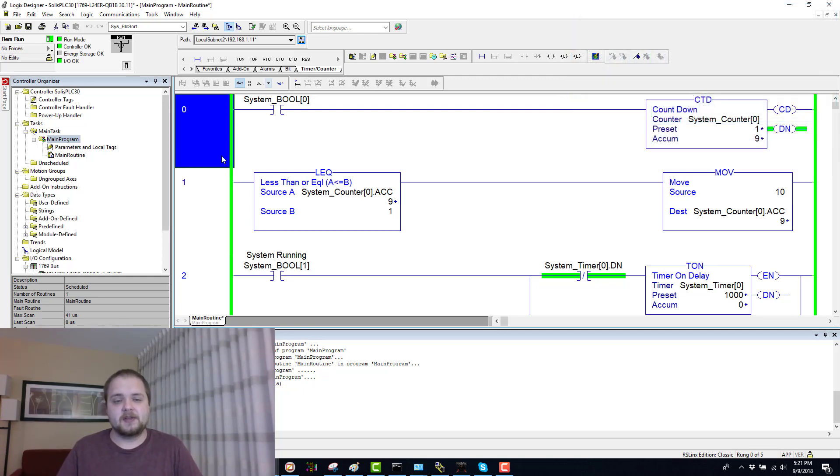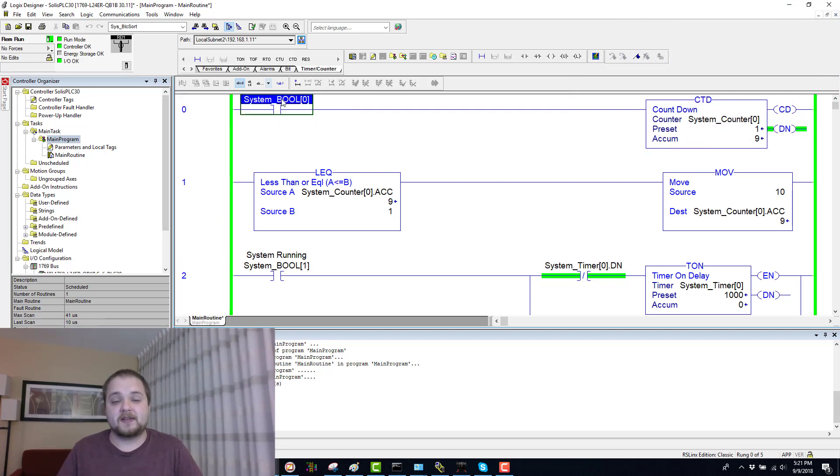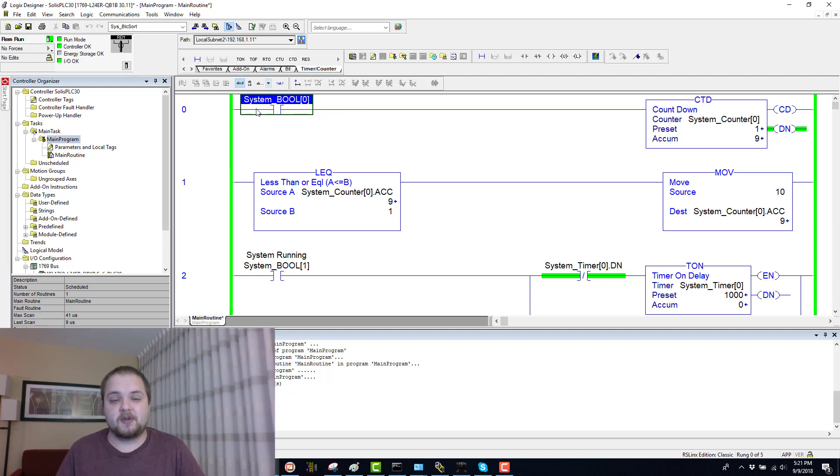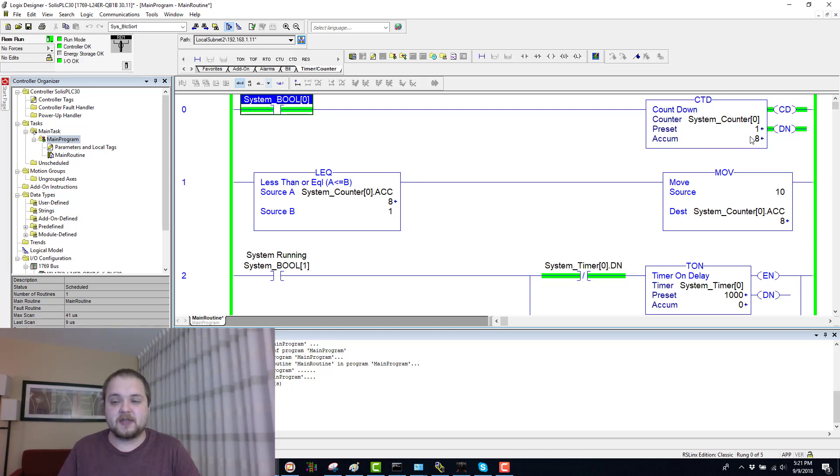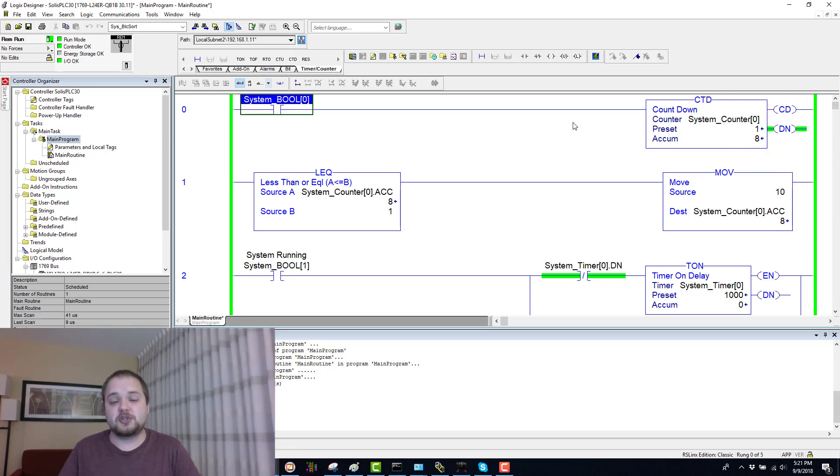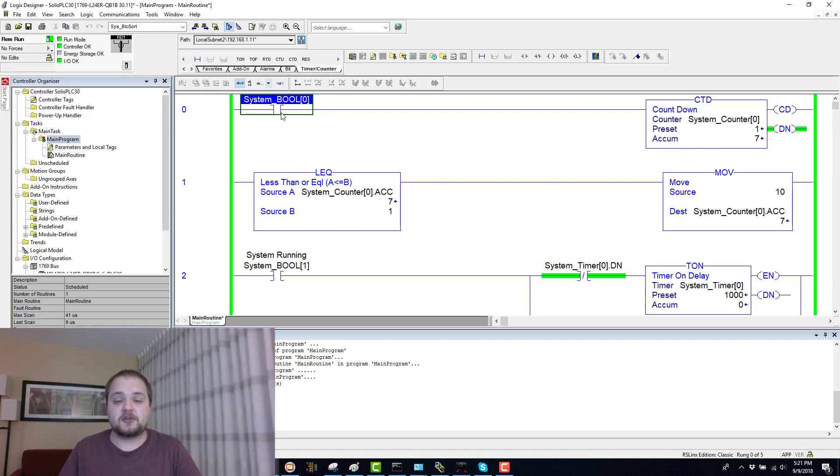On my first rung, all I have is the countdown instruction tied to an XIC, which is going to be the System_Boolean0. As soon as I toggle this instruction, as you would expect, the accumulated value of the countdown timer will go down. It will remain on that value until a transition back to low to high is seen in front of the countdown instruction.